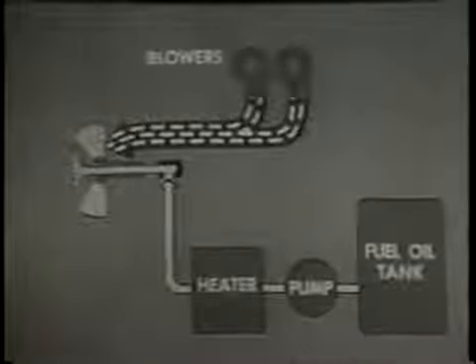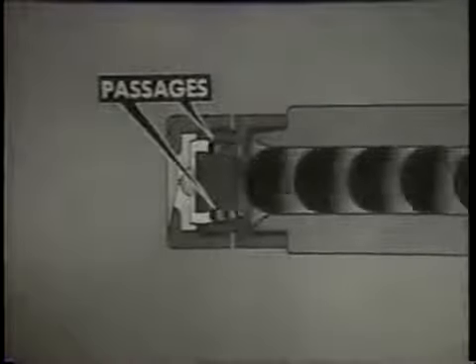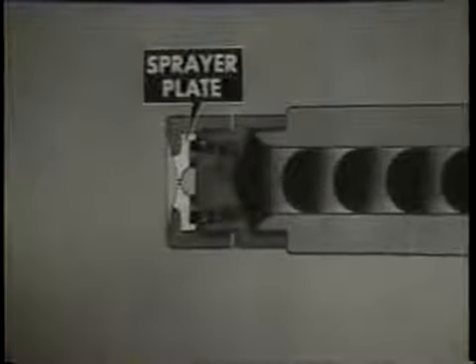The forced draft blowers send a strong blast of air to the burner. The fuel oil pump sends the oil through the heater where the oil is heated to give it good flow quality, then the oil is pumped to the burner. This simplified cutaway of the burner shows how the fuel oil is forced through the burner barrel to the atomizer nozzle, where a series of passages guide the oil to the sprayer plate. The sprayer plate makes the oil rotate at high speed, breaking up the oil into particles. The oil leaves the atomizer as a hollow, mist-like cone or spray.